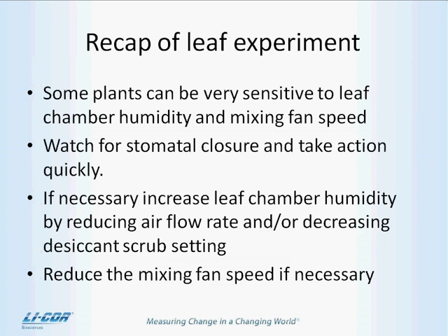Okay, here's a recap of the points that we covered. Some plants such as rice, greenhouse-grown plants, and stressed Mediterranean species can be very sensitive to chamber humidity and leaf chamber fan speeds. So watch for stomatal closure when clamping onto leaves. Take action quickly because stomatal closure can occur very quickly, often in less than 5 minutes, whereas stomates reopening can take 20-30 minutes or more.